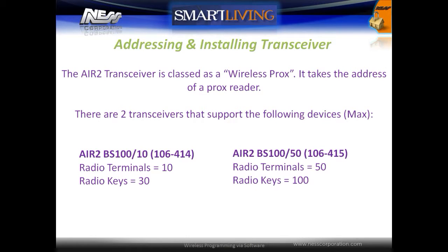The transceiver is classed as a wireless prox and takes the address of a proximity reader. The 10 channel transceiver supports 10 wireless terminals and up to 30 radio keys. The 50 channel transceiver supports up to 50 terminals and 100 radio keys. This will depend on the control panel's total allowable terminals.